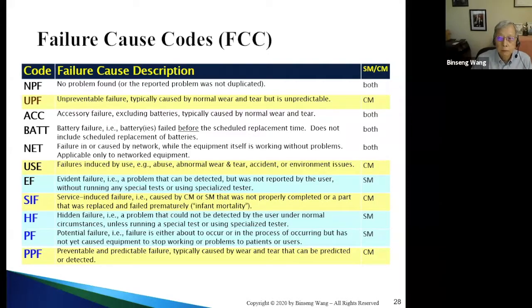And then if you want, you can analyze in more detail later when you have more data. Okay, I'm not going to read every single one, but some are very trivial. No problem found: you schedule maintenance, you go there, everything's fine, you perform the inspection, and you say no problem found. Unpreventable failure, for example, when an electronic component failed; it's unpreventable, nothing I can do about it. Accessory failure, excluding batteries, because battery is a category. Accessories, for example, a pulse oximeter finger probe failing. Rechargeable battery is something that you know well very often has a problem, and that's something we need to document, and we need to see how we can address that.